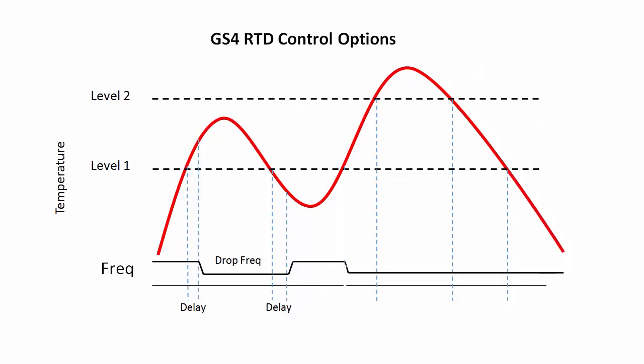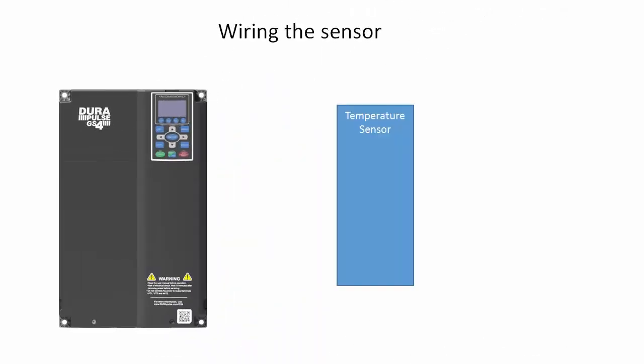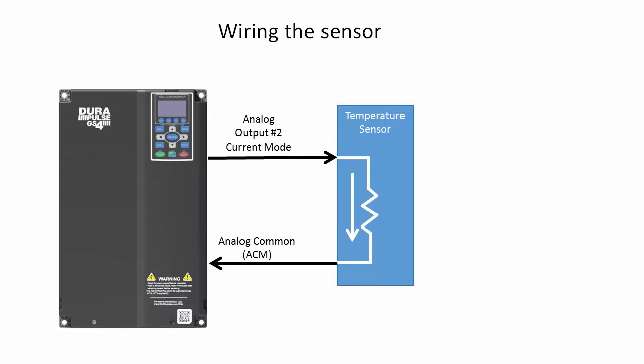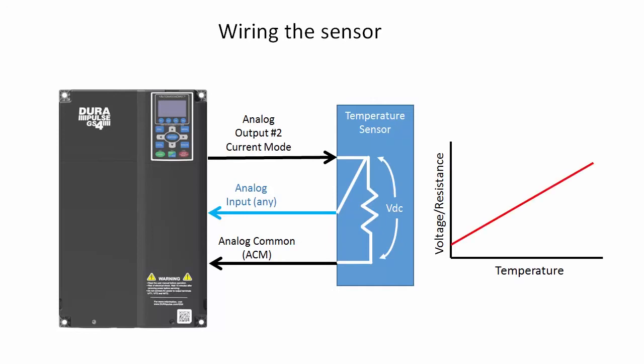Let's do an example using an RTD so we can see how this works. For both types of temperature sensors, connect the device to analog output number 2. Because it can be set up as a true current source that can drive a fixed current through the sensor to create a voltage we can measure with an analog input. And since the resistance changes with temperature, the voltage we read will be proportional to that temperature. You can use any analog input. We'll use input number 3 for this example.